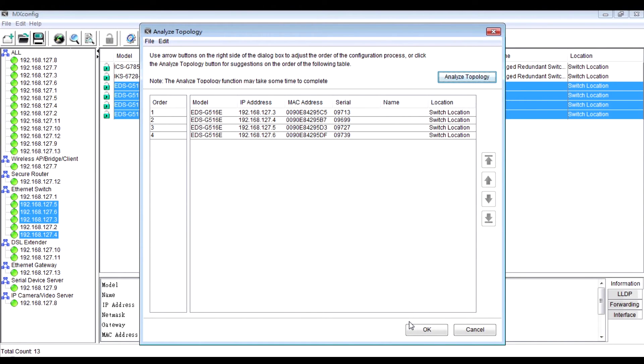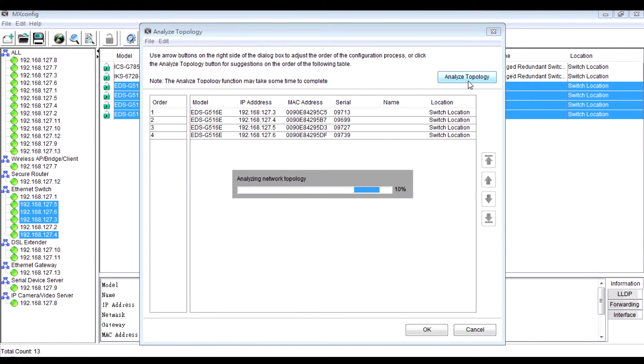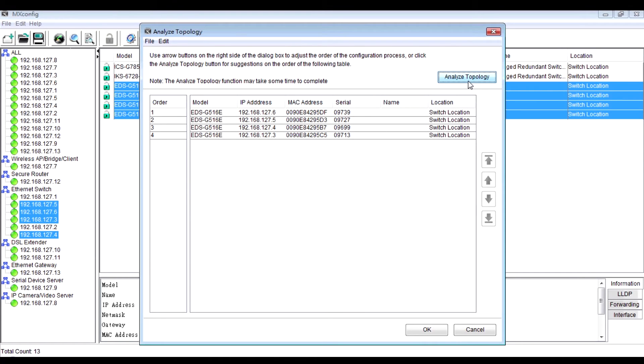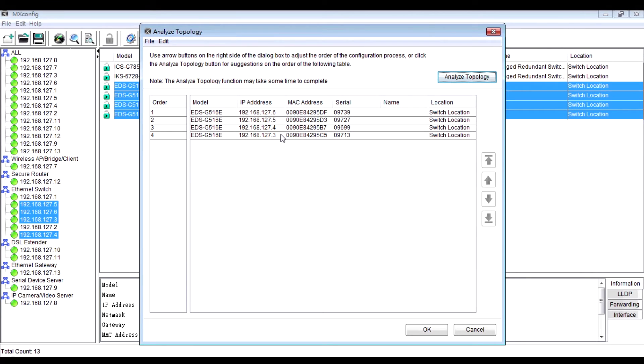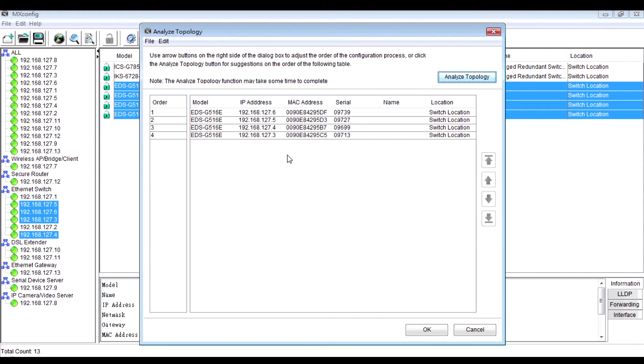Now we click OK. Before we start to configure TurboChain, we have to click Analyze Topology to analyze the link sequence between devices and prioritize the order from farthest to nearest. The farthest devices will be configured first, then the second farthest, and third farthest. In the end, the nearest one will be configured. If we don't follow this kind of order, the farthest one may not be successfully configured because the nearest one finishes the setting and disconnects the farthest one. Especially when we set the redundancy protocol on the connected ports. The Analyze Topology function can make sure that all operations and settings will not be lost by disconnection.